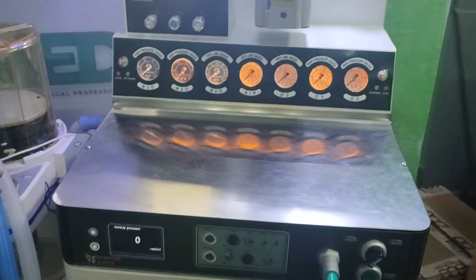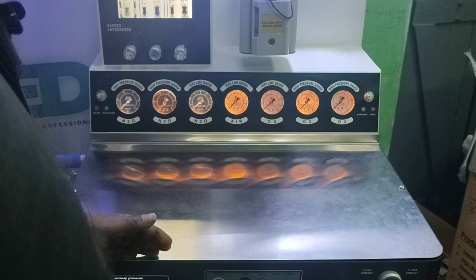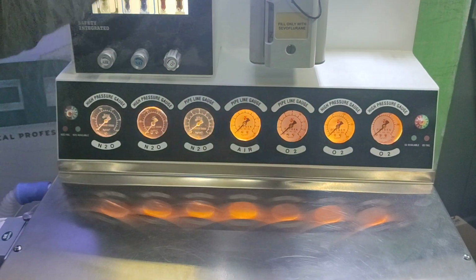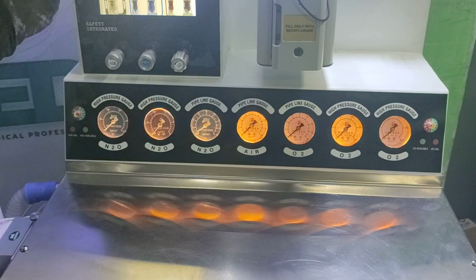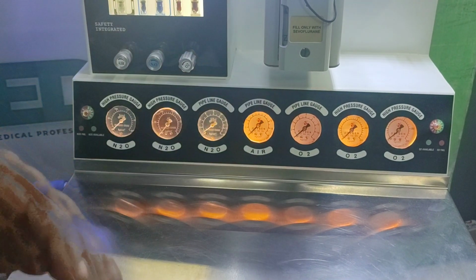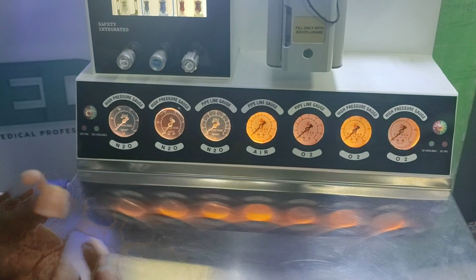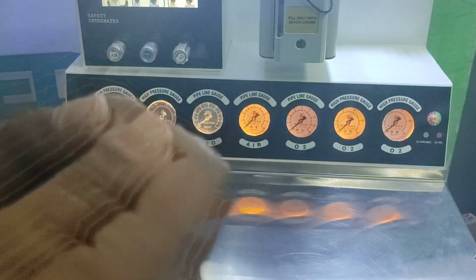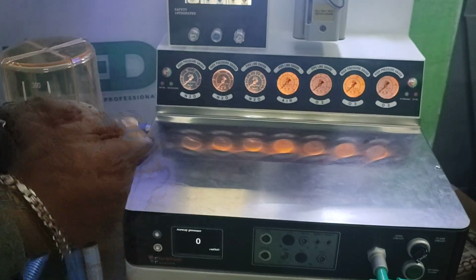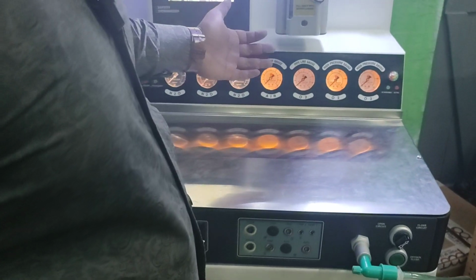Here is the panel for your pressure meters. These machines can be connected to a pressure pipeline, meaning if you have an oxygen pipeline, you can connect it to the pipeline pressure, or you can connect cylinders at the back of the machine. It is very important that you connect cylinders beside the machine and then connect to the air gas supply, so that if there is any fault with the gas supply, the machine can be run with oxygen or N2O cylinders which you put at the back.